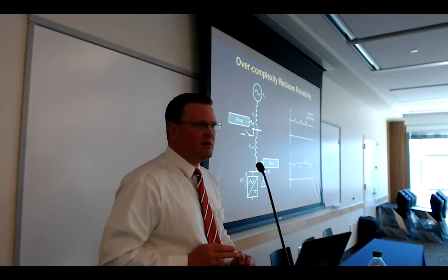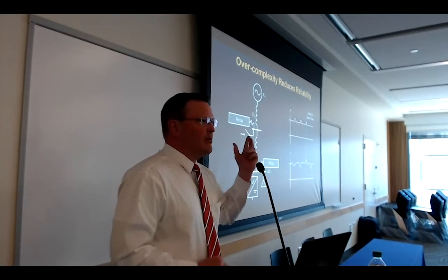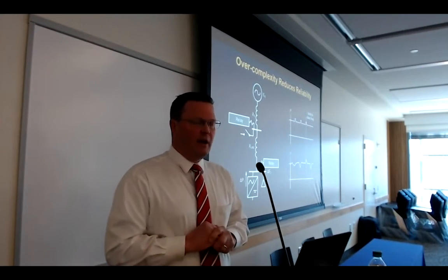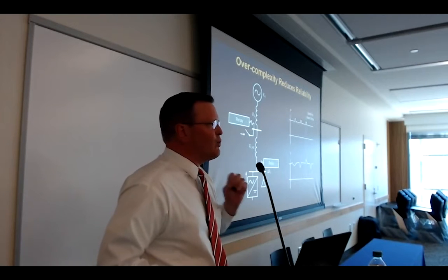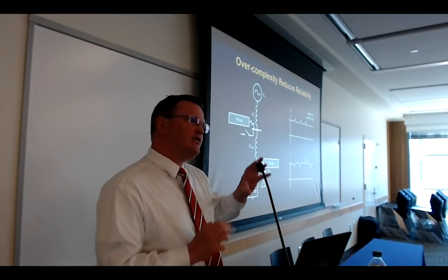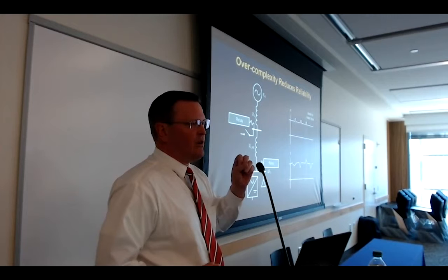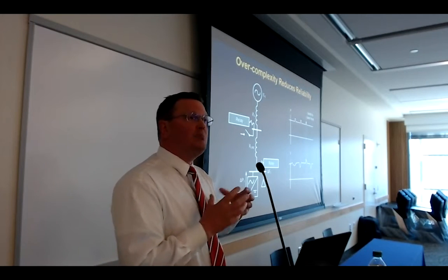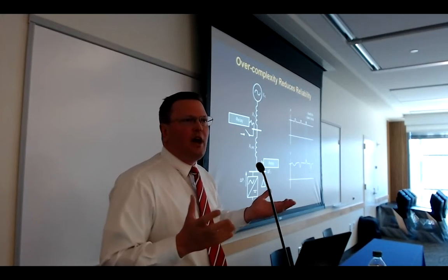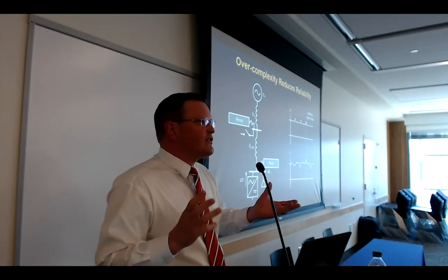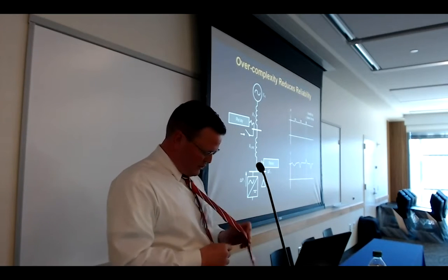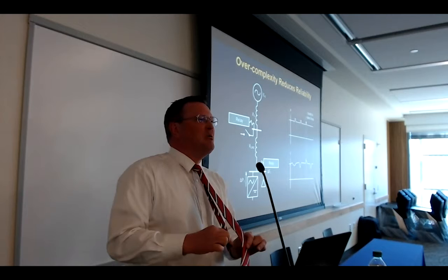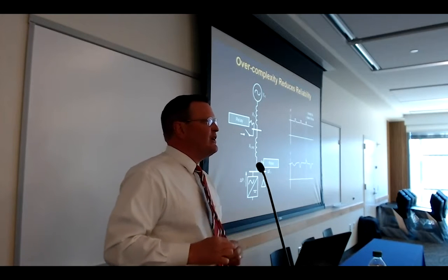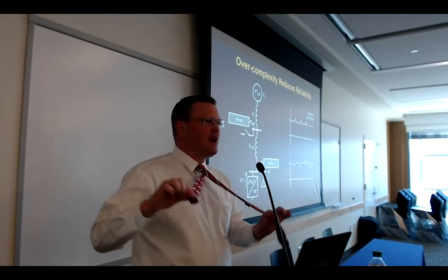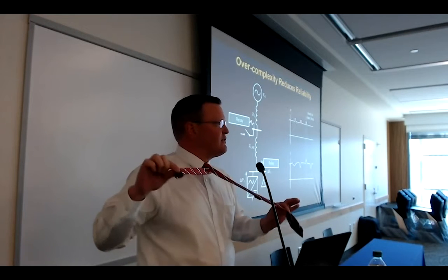Everything is at stake. Okay, here's an example of a well-meaning anti-islanding element pushing against a very weak grid. Not that it's not a weak grid, rather that it's a long or high impedance, a large X Thevenin. Basically, it's natural, as I'll show with my tie example, that with a large impedance between you and your large power system you get large power angle shifts.